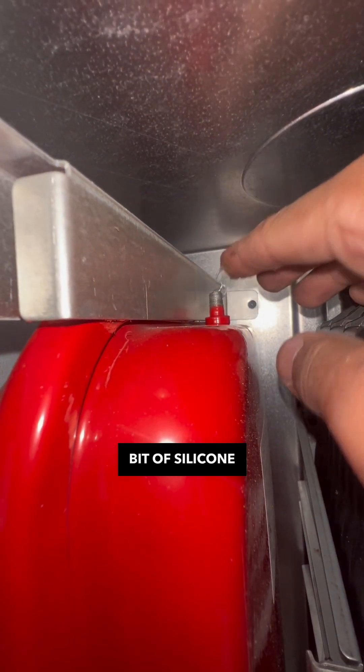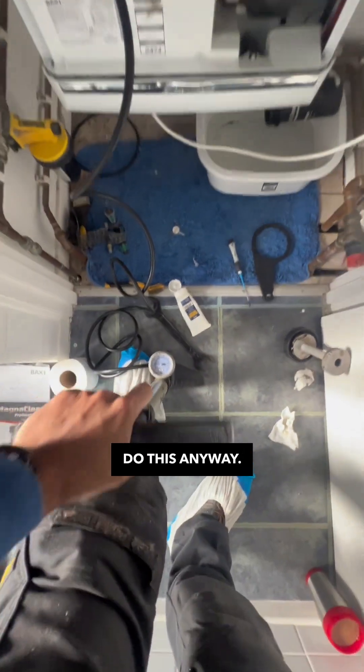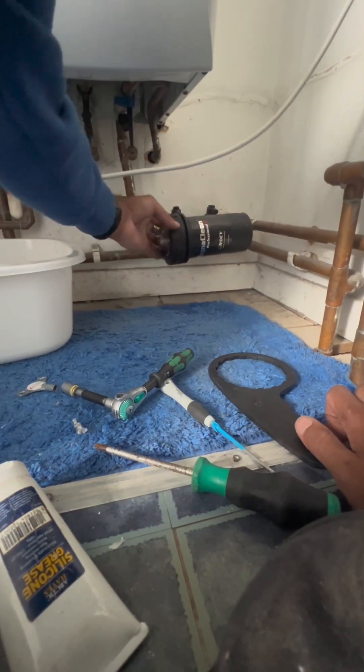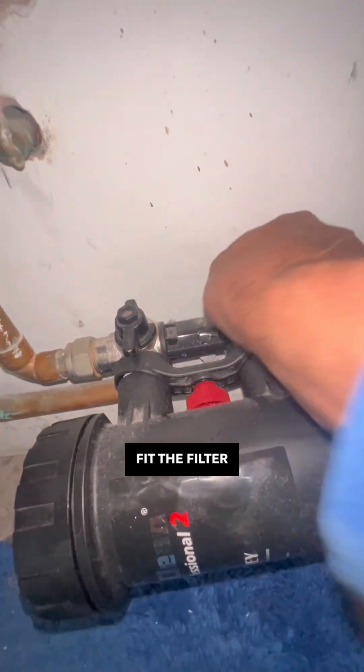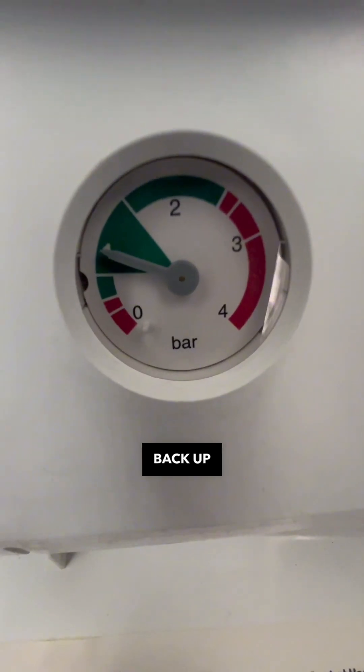I've put a little bit of silicone grease on the expansion vessel pin to stop it from leaking — it was all right but I always do this anyway. Recharge the vessel, get all the water out of the boiler completely, then reverse the process and fit the filter back.